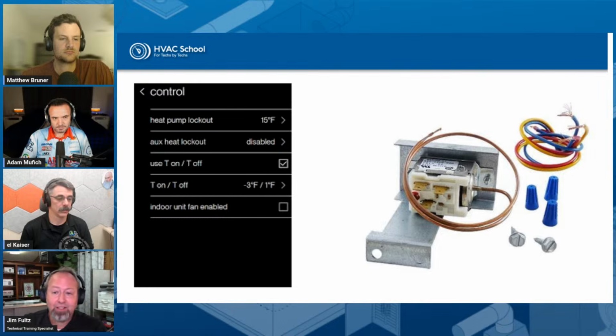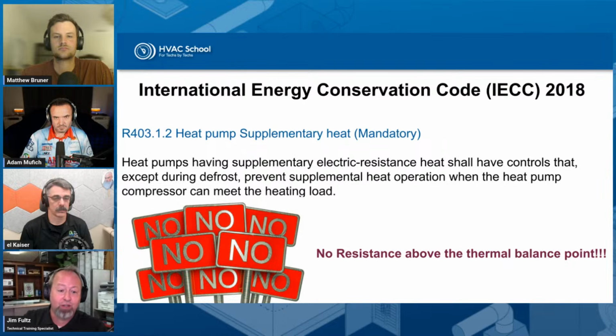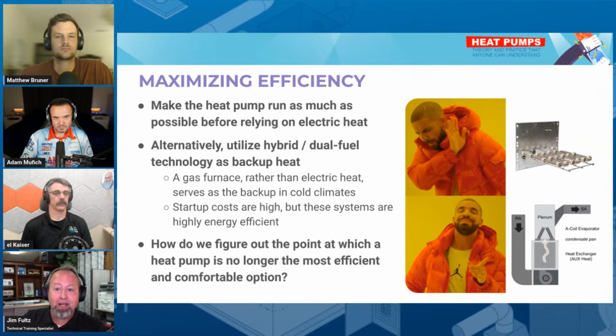And communication with homeowners is always the best solution up front. Not only communication, but documenting that, hey, you're requesting a heat pump. Heat pump heat is known to be less warm than the furnace that you had in there. It's not uncomfortable if it's installed the correct way. And to do that the correct way, you really need to be able to move the air across the walls, across the ceiling, rather than on you.